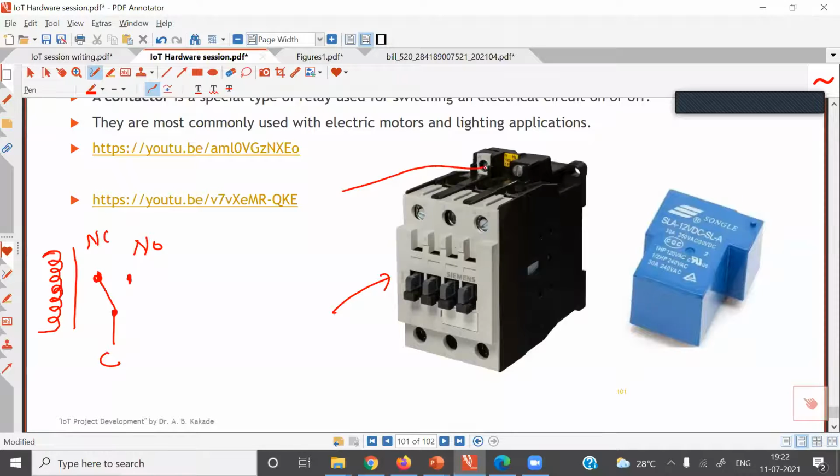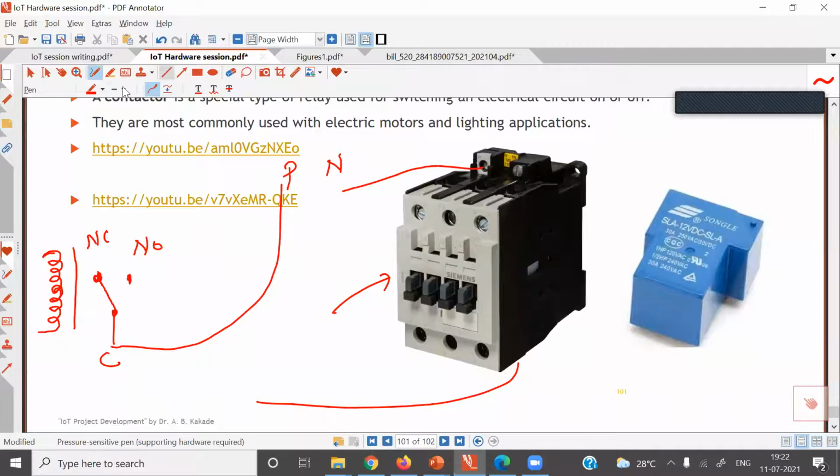one contact of this electromagnet is available here and another one on the bottom side. So what you need to do is, one end you directly connect to neutral, and the phase wire you must first of all connect to the common terminal. Phase must be connected to the common terminal here, and this NO contact must be connected to the remaining wire of this contactor electromagnet.